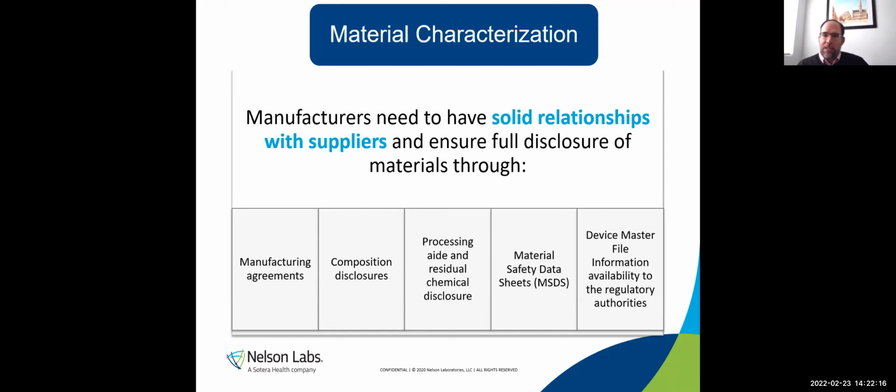A good story about this one is we had a client that was having a manufacturer make glass for their device. And this manufacturer was, for a long time, making glass for them. And my customer would routinely send in some cytotoxicity tests from lot to lot, just to kind of help some kind of control point for their materials. So every lot they got in from this raw glass, they would send us a small portion to do a routine cytotoxicity test on it. And we were doing that for years.